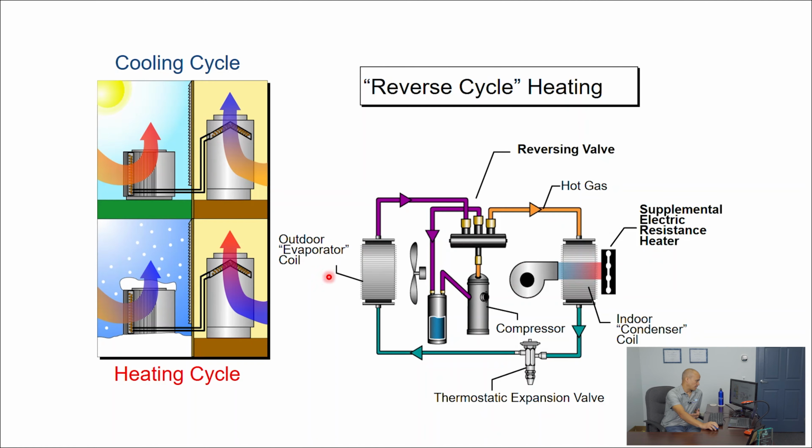Sorry, right here, evaporator coil on the left side. We take that heat and we send it to the outdoor unit. Same thing happens here. Take that heat, send it to the outdoor unit. The outdoor unit, which has the condenser coil, his job is to reject heat. So evaporator coils absorb heat, condenser coils reject heat. They both have a fan on them, right? There's a fan on the evaporator coil, and a fan over here on the other coil. Both have coils, both have fans.